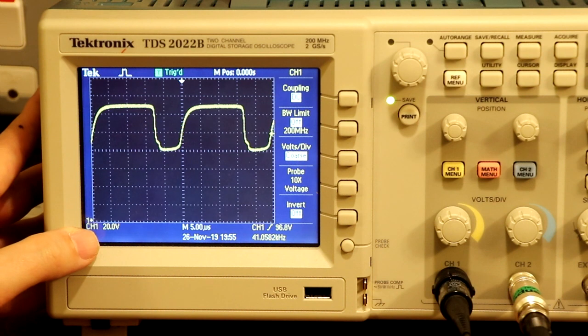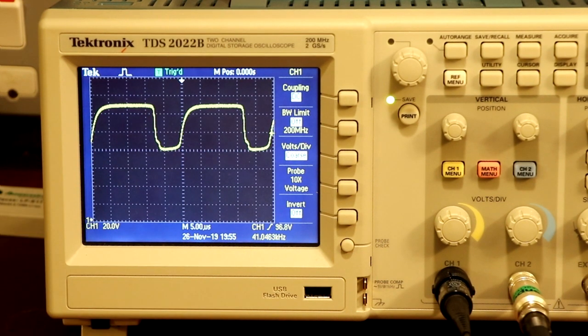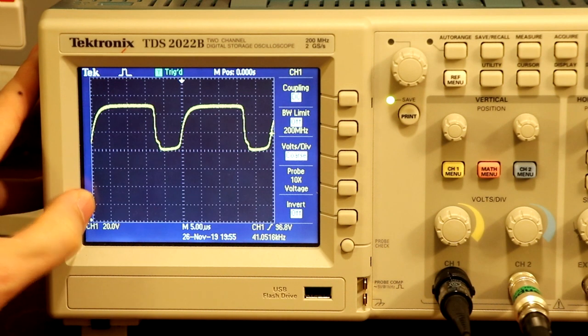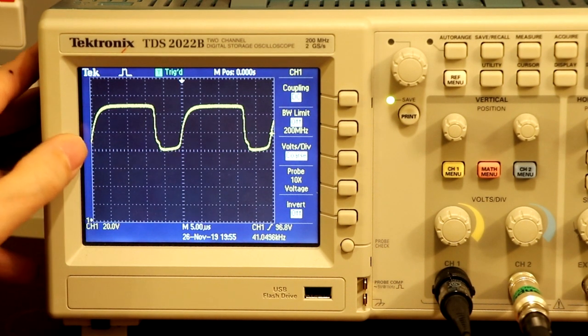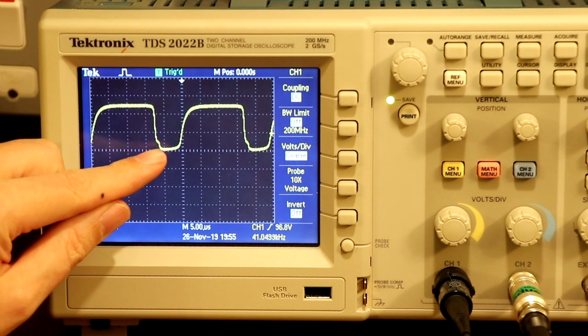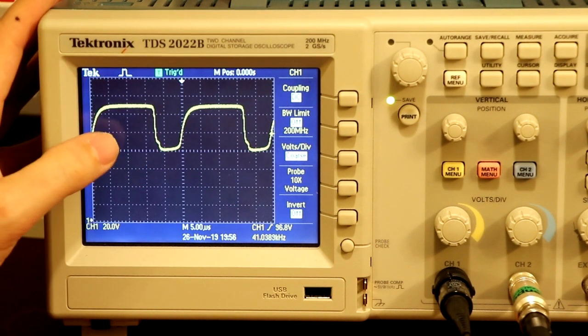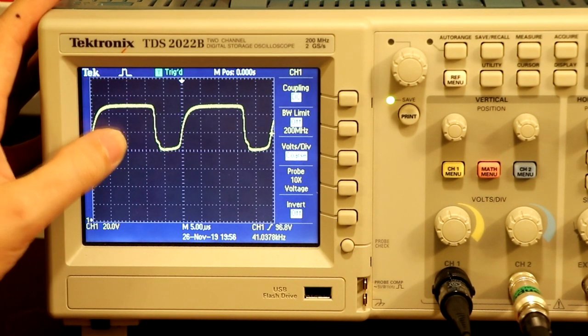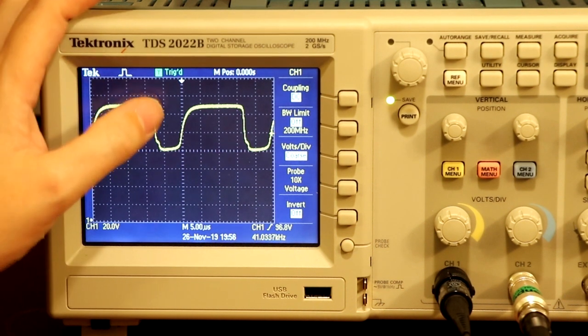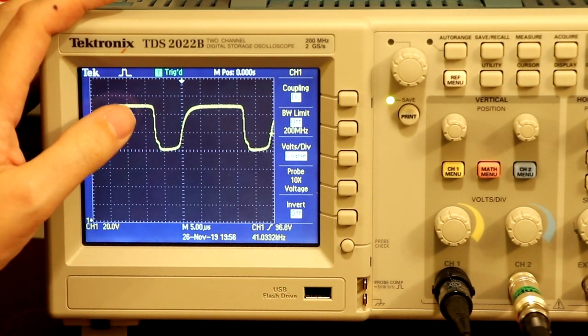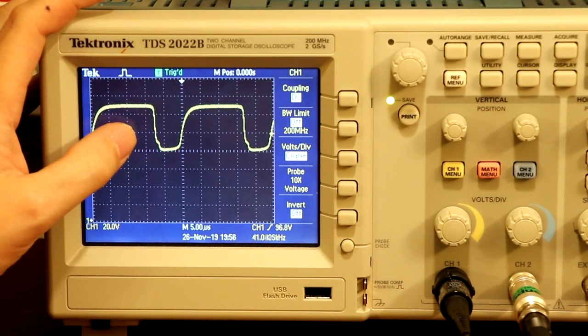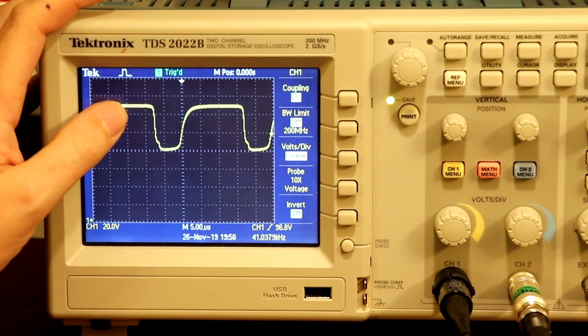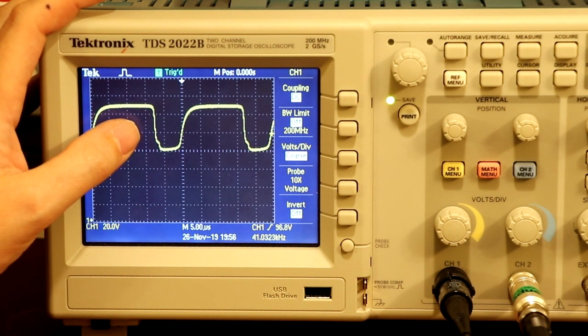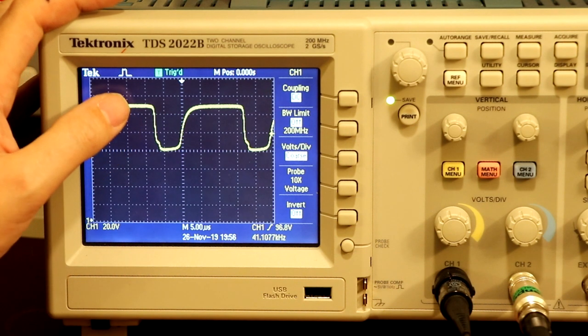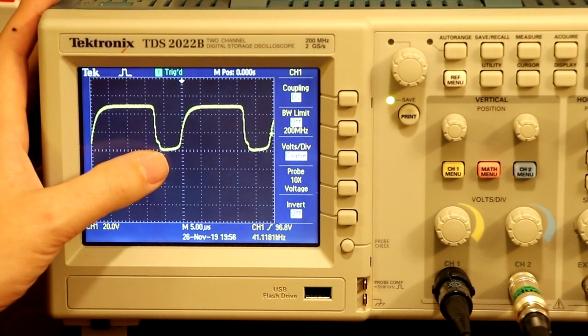So we set the ground reference here at the bottom of the scope. So let me just roughly count up. So we've got 20, 40, 60, 80. So actually the off for our square wave waveform here, it's not at 0 volts, it's actually at 80 volts. And then the next one is 100, and then 120. So basically the output of our square wave here varies between 120 and 80 volts, and this is being fed to actually turn our VFO on and off. So interestingly enough, we're not actually switching off all the drive voltage to the VFO, we're just dropping it from 120 volts back down to 80.